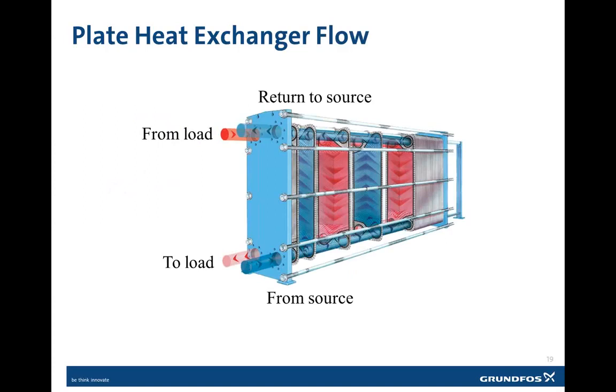Now there's two important factors when sizing a plate heat exchanger, and that's the pressure drop and the approach temperature. The approach temperature is the temperature difference between the source fluid and the fluid delivered to the load. So a very close approach of around 2 degrees Fahrenheit can then be achieved without a large pressure drop throughout the system.